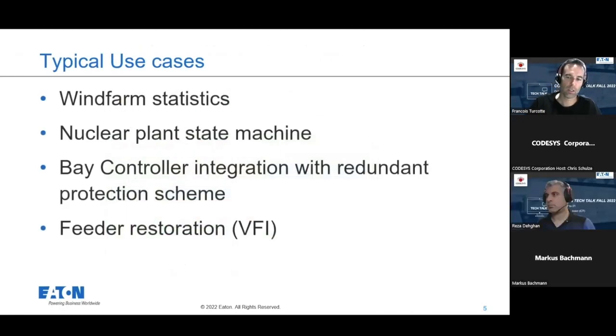Now, as far as the typical use case goes, I discussed the wind farm statistics. We accumulate values on the device itself, and then every 10 minutes, or every X minutes, we can send them to the utilities that require those values, and they use them to calculate, for example, the forecast for power generation, or what the wind is right now, and how much they need to slow down the pace of production. If any decision needs to be taken, it's good for them to know this information in advance. That's what CODESYS can provide them, that kind of statistics.